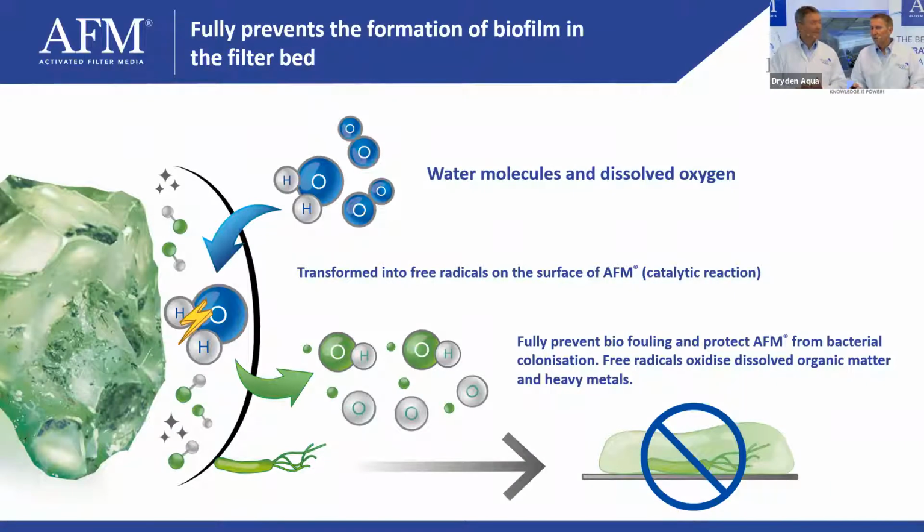The only other filter media that I know that is resistant to biofouling is diatomaceous earth, I believe, to some degree, right? That's true. But we know the downsides of DE. We covered that in an earlier session, right? But definitely not sand. And AFM is in a way quite similar, just ours is easier to use and less costly. Not zeolite. No, definitely not zeolite. Zeolite is perfect for the first 3 months, but then you get heavy biofouling.